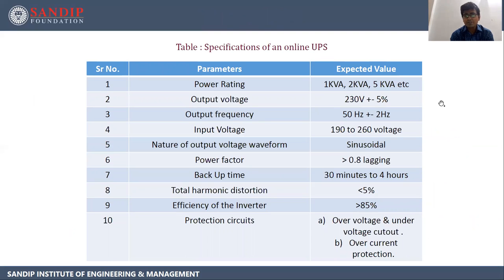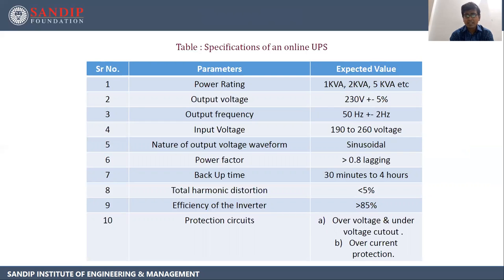Let's see the specifications of online UPS. Power rating: online UPS comes with 1 kVA, 2 kVA, 5 kVA. Output voltage is 230 V with a variation of plus or minus 5%. Output frequency is 50 Hz with a variation of plus or minus 2 Hz. Input voltage is 190 to 260 V. Nature of output voltage waveform is sinusoidal. Power factor is greater than 0.8. Backup time is 30 minutes to 4 hours. Total harmonic distortion (THD) is less than 5%. Efficiency is greater than 85%, and protection circuits include over voltage and over current protection.